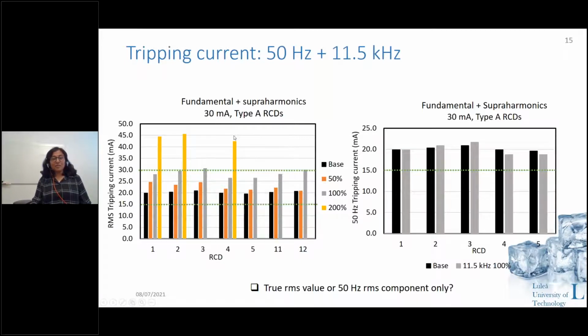But this is just the RMS value, including the RMS value of 11.5 kilohertz or supraharmonics. Whereas on the right hand side, for the same base case and 100% of supraharmonics at 11.5 kilohertz, this is just the 50 hertz component that is there, and the 50 hertz component is within the range for all the RCDs. So then it is not false tripping.